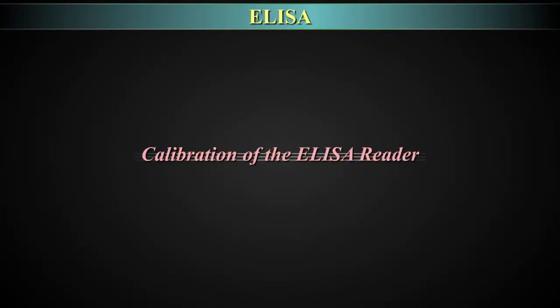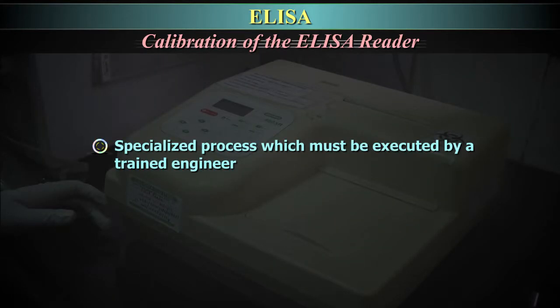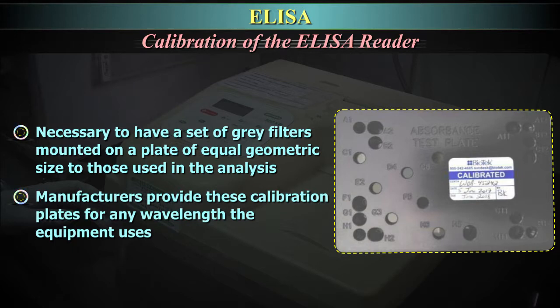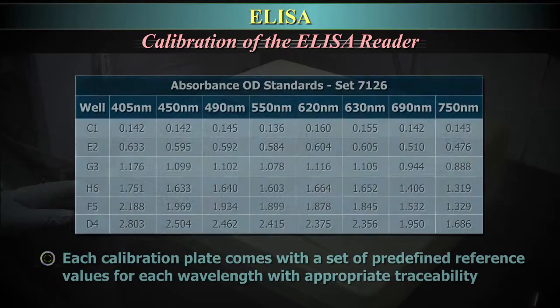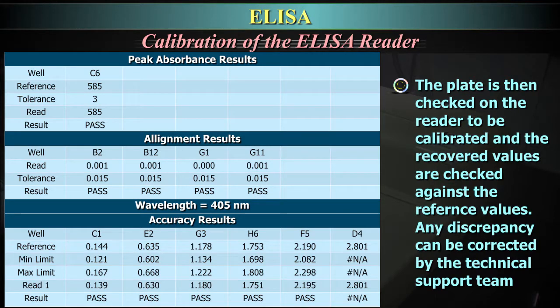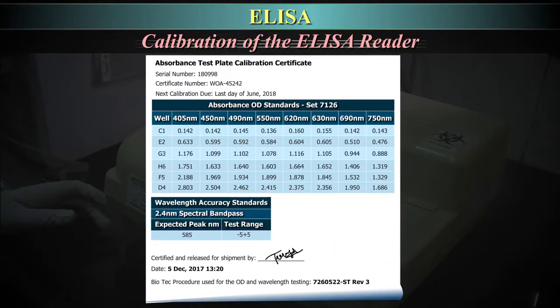Calibration of the ELISA reader. The calibration of a microplate reader is a specialized process which must be executed by a trained engineer. In order to do the calibration, it is necessary to have a set of grey filters mounted on a plate of equal geometric size to those used in the analysis. Manufacturers provide these calibration plates for any wavelength the equipment uses. Each calibration plate comes with a set of predefined reference values for each wavelength with appropriate traceability. The plate is then checked on the reader to be calibrated and the recovered values are checked against the reference values. Any discrepancy can be corrected by the technical support team. It is essential to get a certificate of calibration, which will also show the next due calibration date.